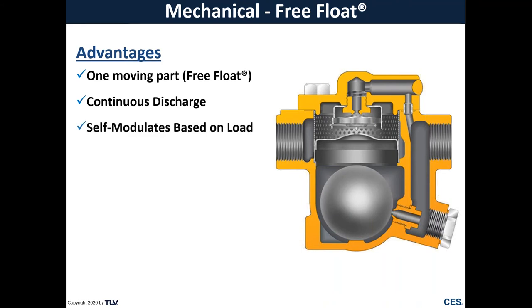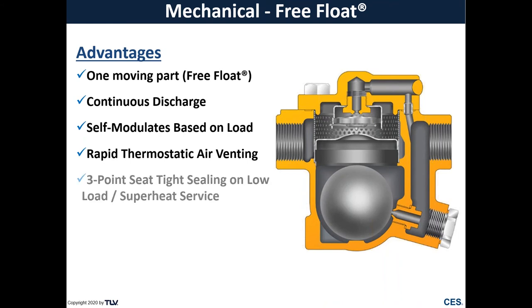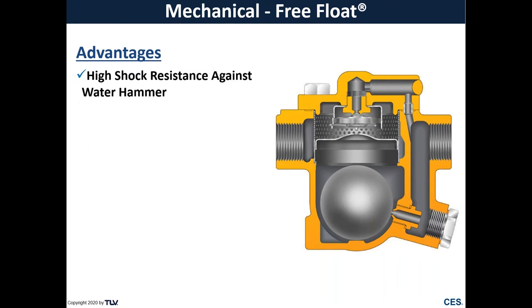Continuous discharge, and it's going to self-modulate based on how much condensate's coming in. You saw in the animation when there was a lot of condensate coming in, that float fully lifted off the orifice. As well as the X element is very receptive to any air that enters into the steam trap, it's going to open up and allow that air to vent. During startup, that X element's going to be wide open as well. Some of our free float models do include a 3-point seating. And so this is for your superheat conditions or your low load conditions where you may not have that water prime, this three-point seating will ensure a very tight shutoff with that float and the orifice. Additional advantage, we've taken great care to make sure that this trap has a high shock resistance to help mitigate any damage from water hammer.